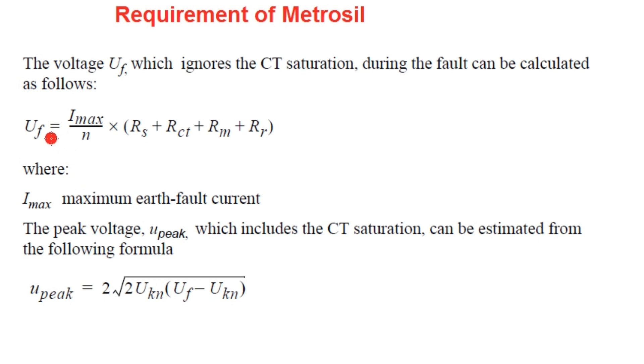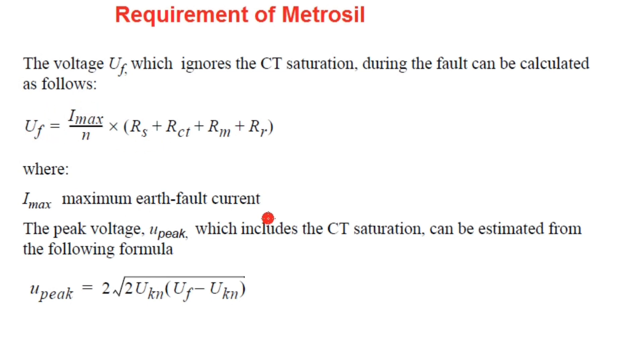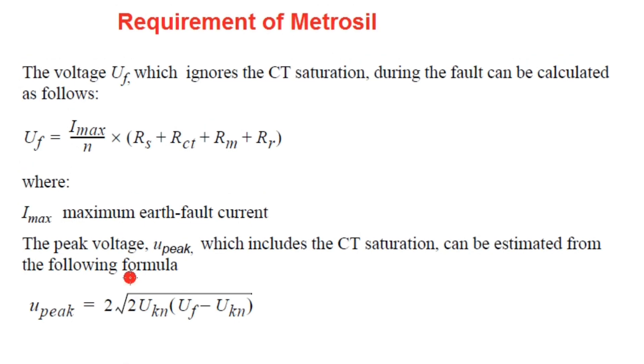Uf is given by: Uf = (Imax / n) × (RS + RCT + Rm + Rr), where RS is the stabilizing resistance, RCT is the CT internal secondary resistance, Rm is the loop resistance from the CT secondary circuit to the relay, and Rr is the relay burden in ohms. Imax is the maximum earth fault current. If the peak voltage exceeds 3 kV, a metrosil is required connected in parallel with the resistance and relay coil, to protect relay insulation under internal fault conditions.